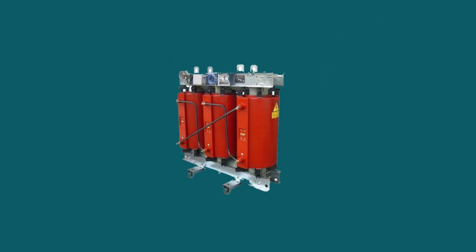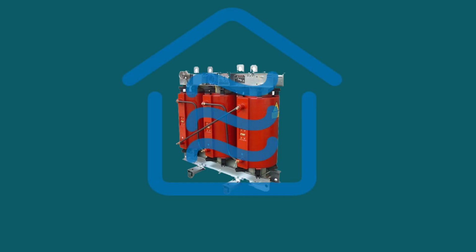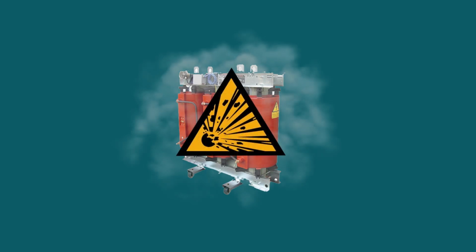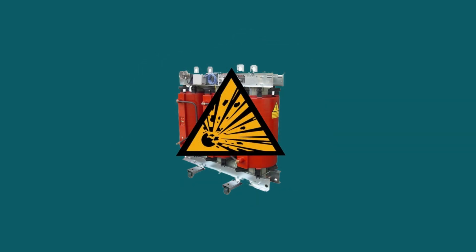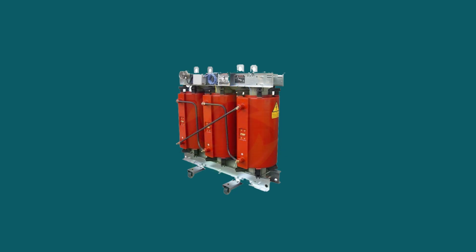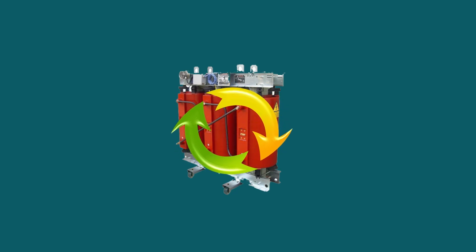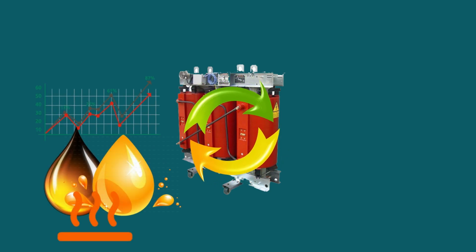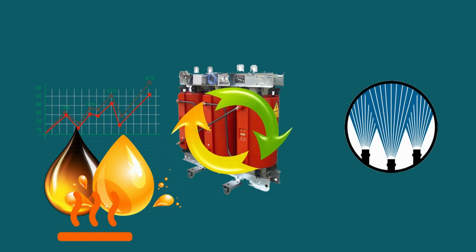The disadvantage of drying with hot air is the non-uniform warm-up of the insulation. The efficiency of vacuum ovens significantly depends on the method of heating the windings insulation. The method of drying in the vapor phase requires expensive equipment of special design, since a solvent is an explosive substance. And the circulation of hot dehydrated oil with spraying and vacuuming is characterized by a long oil heating process, a high energy consumption, and the need to install spraying nozzles inside the winding of each transformer.